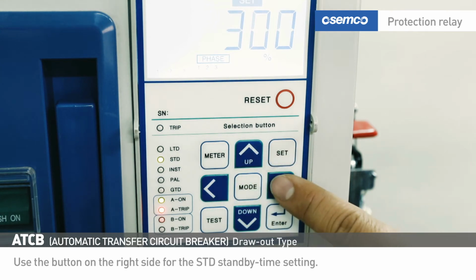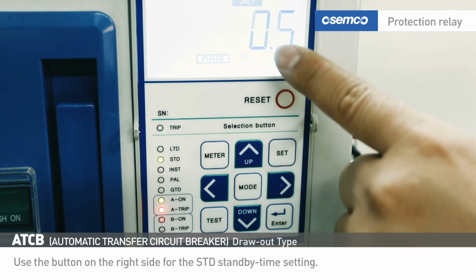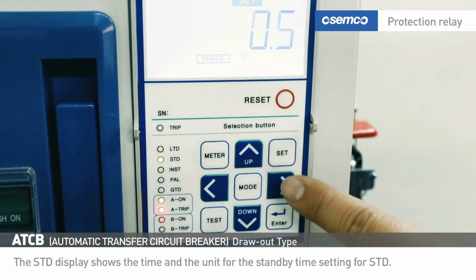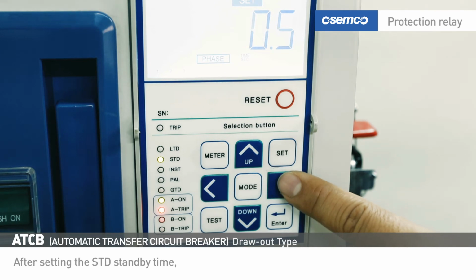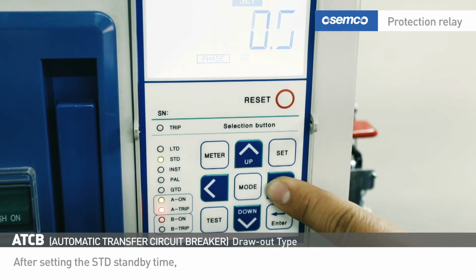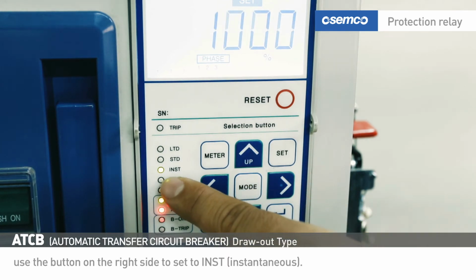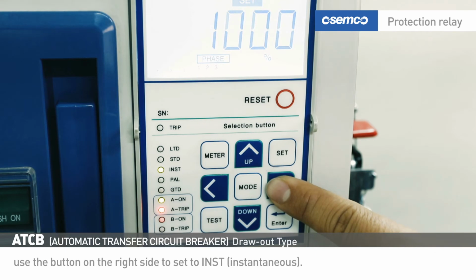Use the button on the right side for the STD standby time setting. The STD display shows the time and the unit for the standby time setting for STD. After setting the STD standby time, use the button on the right side to set the INST, instantaneous. Use the up-down button to select a value for the INST set current.